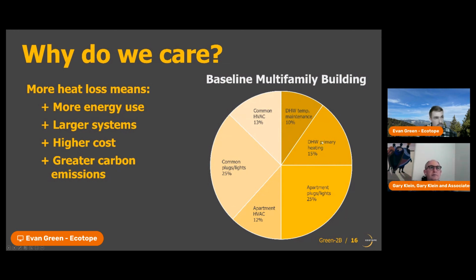So if we think about applying heat pump water heaters as a way to decarbonize our buildings, we have to think about how these are sized and how it affects these systems, and why this has been such an important issue for me since the beginning. We have to keep in mind that a typical gas water heating system is usually sized to handle the all-time worst peak hot water usage, probably a peak hourly usage that building will see. So these gas systems are sized with a really high capacity, and this small, consistent temperature maintenance load is pretty small relative to that giant all-time peak water usage.